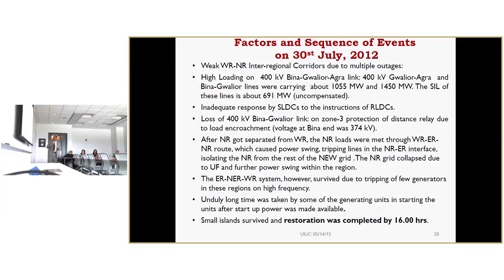Now, these are the main findings. I just wanted to emphasize that our operator was allowing the power flow up to the thermal limit, which was quite high. The SIL, the surge impedance loading of the line, is 691, and the power which was flowing in that line was 1450 megawatt, which is quite high compared to the SIL. So immediately it was revised. And then 2:30 was the blackout, and at about 16 hours in the afternoon, the power was restored.